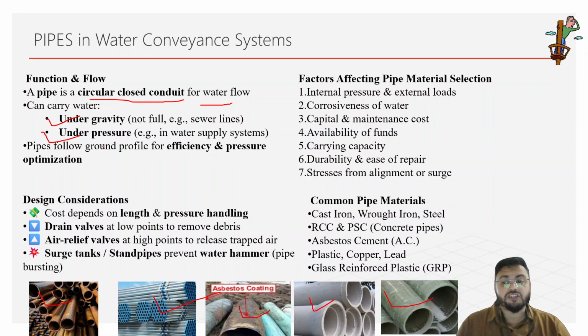For design, we have to consider cost, length of the pipe and pressure handling capacity. If the pressure handling capacity is exceeded, the pipe bursts. Drain valves are provided at low points to remove debris. If debris is not removed, the pipe may choke or its water carrying capacity gets reduced. Air relief valves at high points release trapped air and prevent vacuum in the pipe. Surge tanks and stand pipes are required to prevent water hammer effect and pipe bursting.